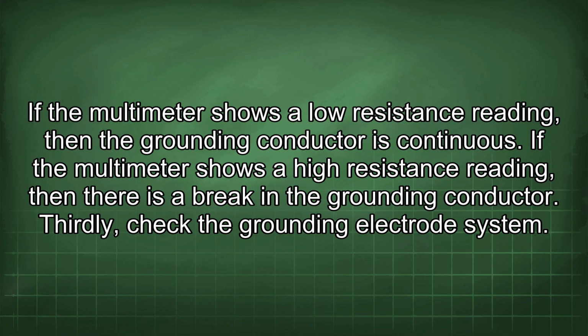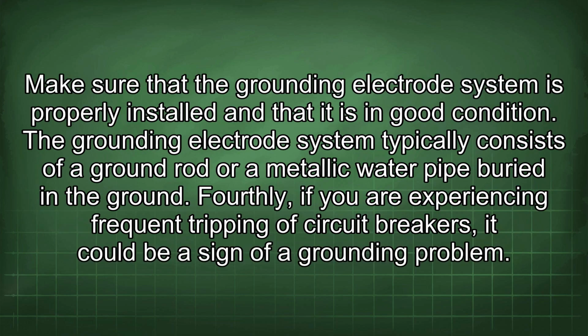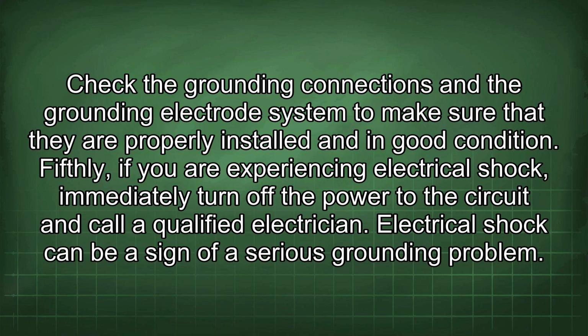Thirdly, check the grounding electrode system. Make sure that the grounding electrode system is properly installed and that it is in good condition. The grounding electrode system typically consists of a ground rod or a metallic water pipe buried in the ground. Fourthly, if you are experiencing frequent tripping of circuit breakers, it could be a sign of a grounding problem. Check the grounding connections and the grounding electrode system to make sure that they are properly installed and in good condition. Fifthly, if you are experiencing electrical shock, immediately turn off the power to the circuit and call a qualified electrician. Electrical shock can be a sign of a serious grounding problem.